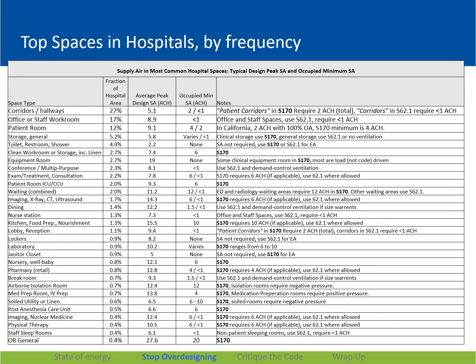Now, I spent a whole year in 2019 collecting data on designs. We did about 1 million square foot of air handler projects in 2019. Every time we did a project, I logged the room names and the square footage and the design CFM into this nice database. So these are the top 30 spaces, top 30 space types in hospitals by frequency. The first thing I want to point out here is all the way at the bottom. Operating rooms are on the bottom of this list of the top 30.